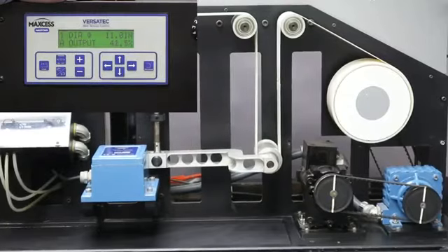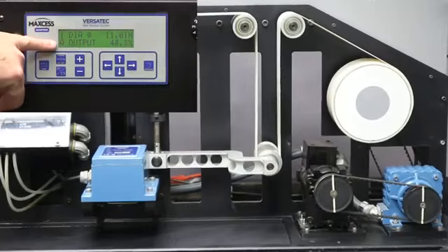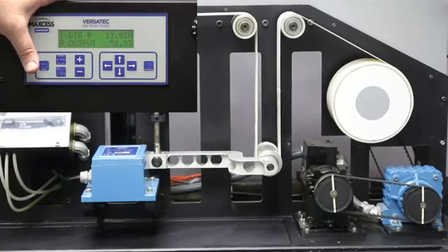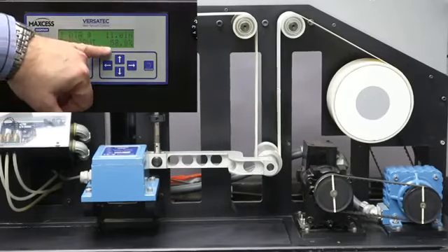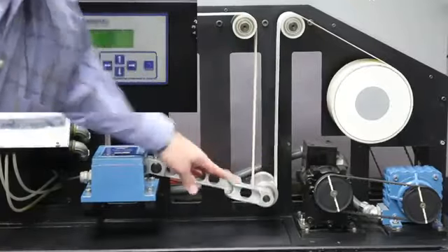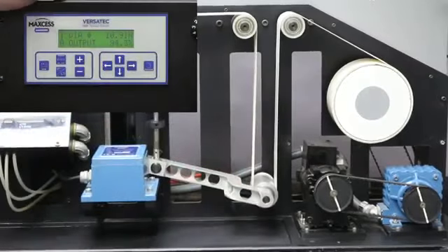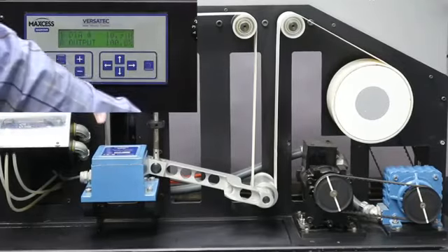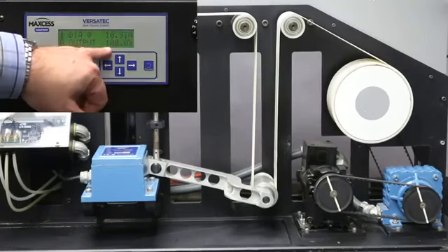I turned the motor off, but I did not turn the control loop off. Note that I'm still in automatic. This control does not know that the machine has stopped because I didn't tell it. And you can see it's integrating up right now through 60%, and if it had stopped low, it's going to go even faster. So right now, the operator has stopped the machine just by stopping the web. Didn't turn the control loop off. Now when he goes to turn that machine back on, look where our output has gone. It's gone clear back up to 100%.